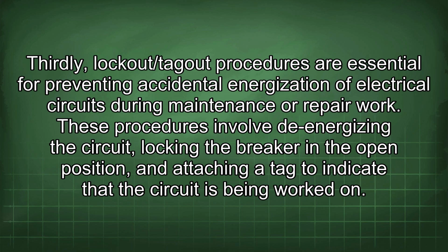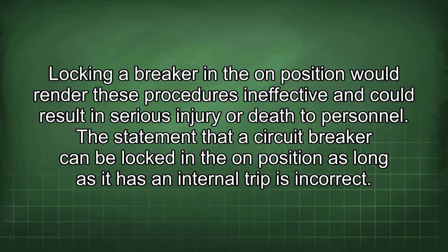Thirdly, lockout/tagout procedures are essential for preventing accidental energization of electrical circuits during maintenance or repair work. These procedures involve de-energizing the circuit, locking the breaker in the open position, and attaching a tag to indicate that the circuit is being worked on. Locking a breaker in the on position would render these procedures ineffective and could result in serious injury or death to personnel.